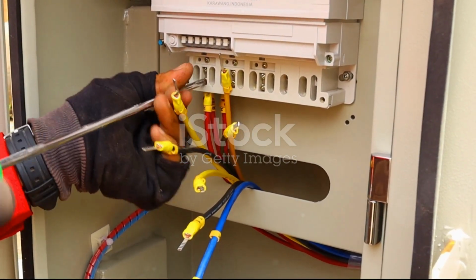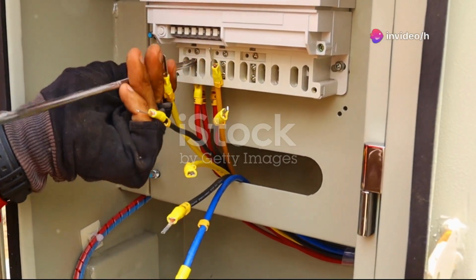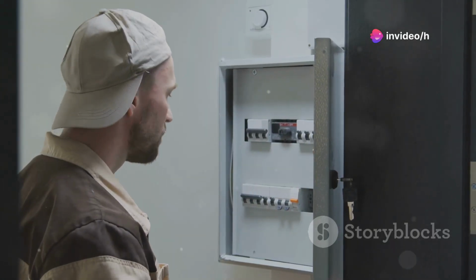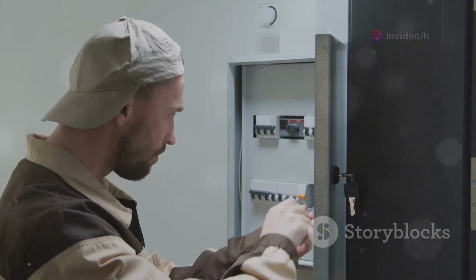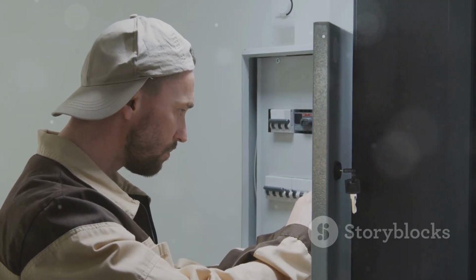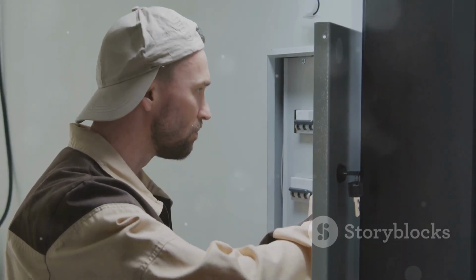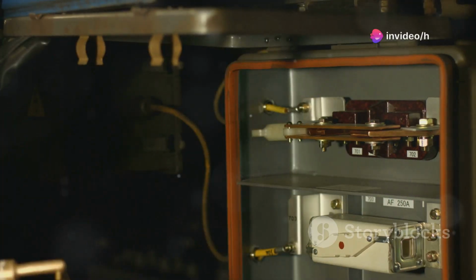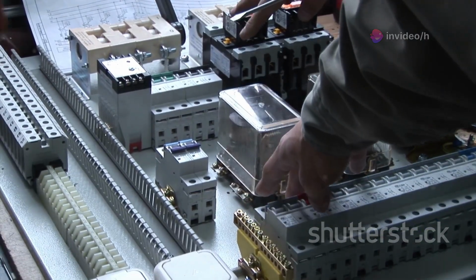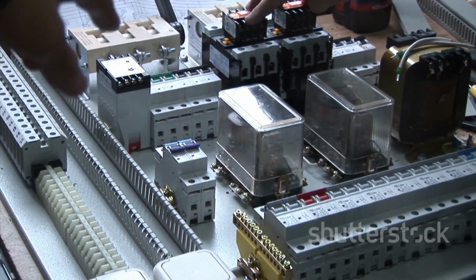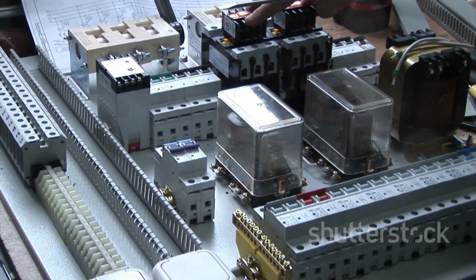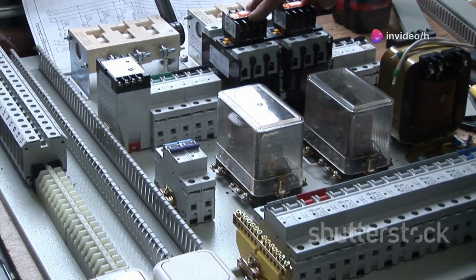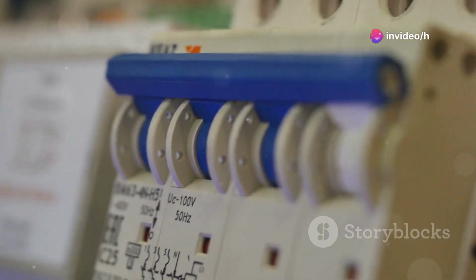Now, let's focus on installing the panel's safety core, RCCBs and MCBs. These components are the backbone of electrical safety in any industrial setup, and their correct installation is absolutely vital. Take your time to ensure each device is properly seated and securely fastened. The RCCB, or residual current circuit breaker, is your first line of defense against electrical hazards. It constantly monitors the flow of current and instantly cuts off power if it detects even a small leakage, protecting lives from electric shocks and preventing potential fires. This quick response can be the difference between a minor incident and a major disaster.